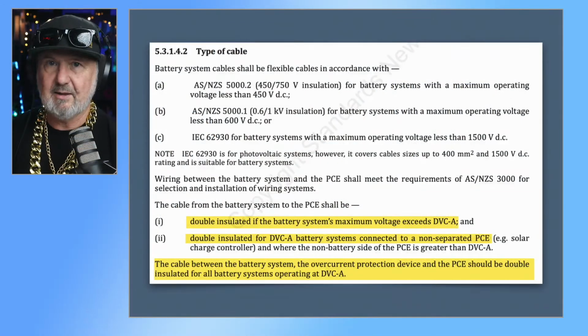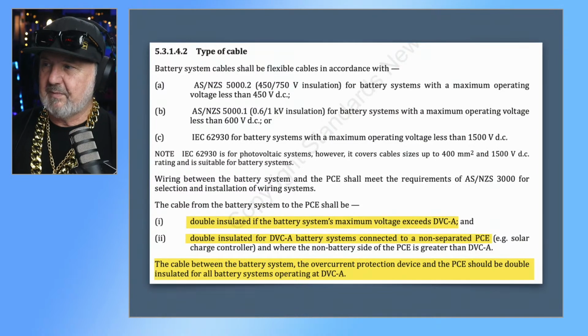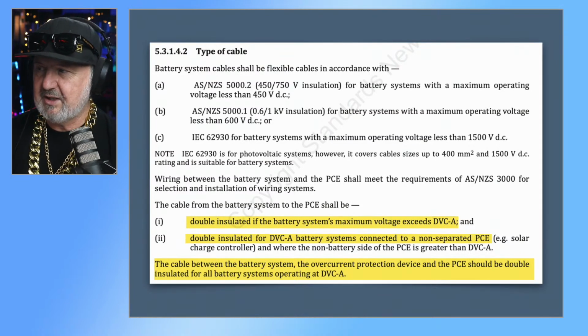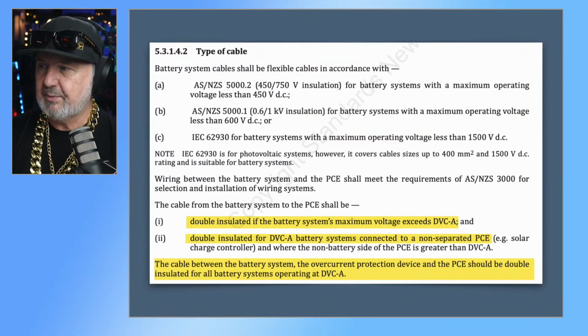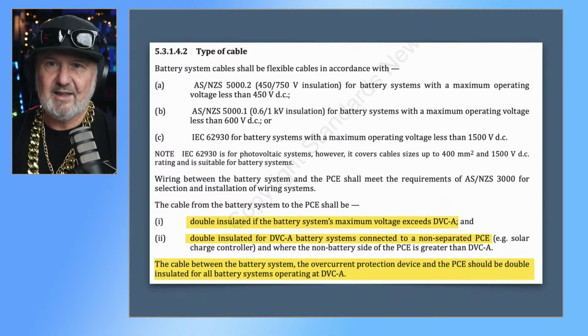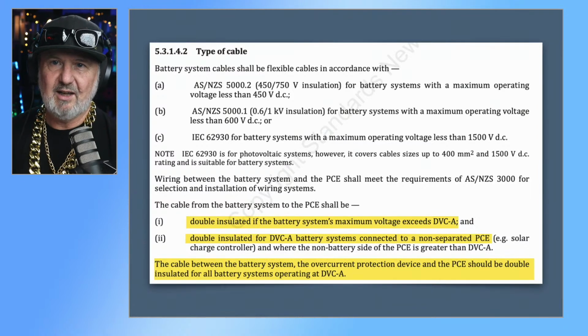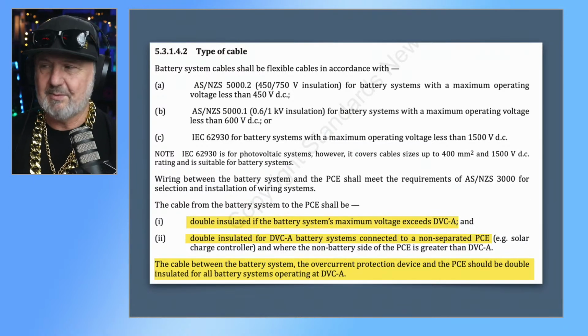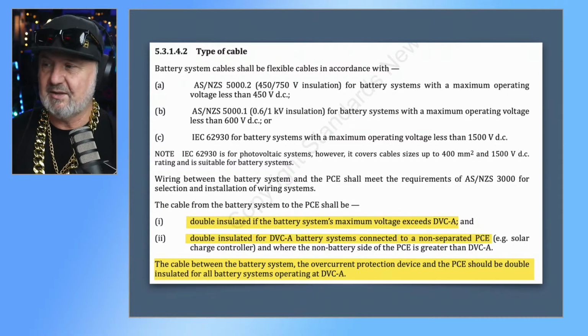about galvanic isolation. Okay, so now we're going to get on to current carrying capacity. Let me bring that one up. Current carrying capacity of the pre-assembled battery system's cable to the overcurrent protection device. So you've got an overcurrent protection device external to the battery system, but there's going to be a cable from the battery system to that device.